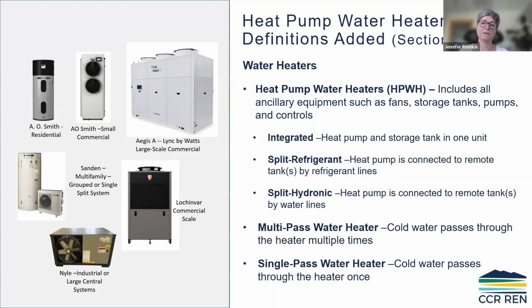So there's a lot of different types of heat pump water heaters out there. Integrated is this type here where the heat pump and the tank are all integrated into one appliance. And that's typically for small commercial and residential projects. And then the split systems, you can have either a split refrigerant or split hydronic. And I'll show you a picture of those. Split just means there's an outdoor unit and the heat pump and the tank are separate.